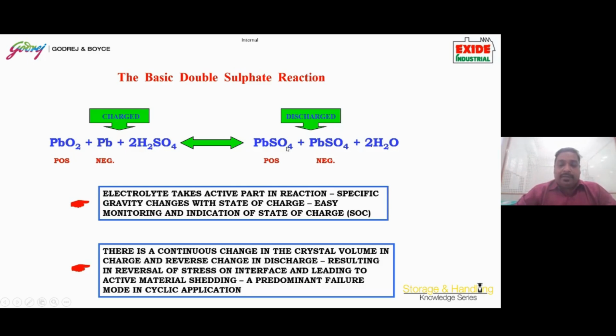The PbSO4, lead sulfate, is not a very battery-friendly component, because in due course of time it gets hardened on the positive and negative plates, and once hardened it is very difficult to remove from the surface. This increases the internal resistance and reduces the capacity of the battery over time. So the first point of maintenance we always tell customers is never allow your battery to remain in a state of discharge or partial charge for a prolonged duration, because this will attract PbSO4, lead sulfate, which is very harmful for the life and performance of the battery.